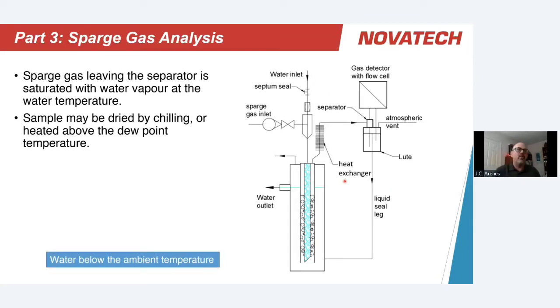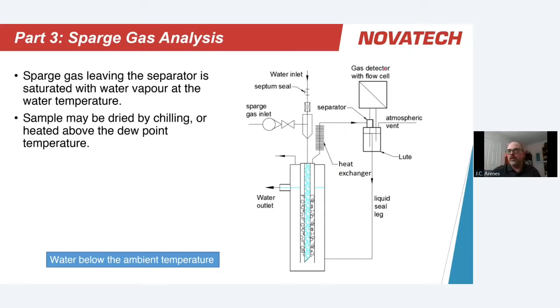In the case where the incoming water temperature is below ambient conditions, the approach is much simpler. We simply need to bring the gas temperature up as quickly as possible away from the dew point temperature, which can be done easily with a finned heat exchanger to bring the gas temperature up to room temperature, and then carry on to whatever detection method is used.